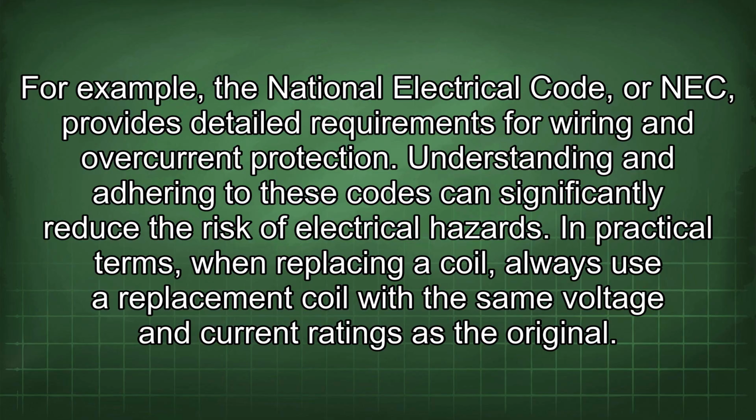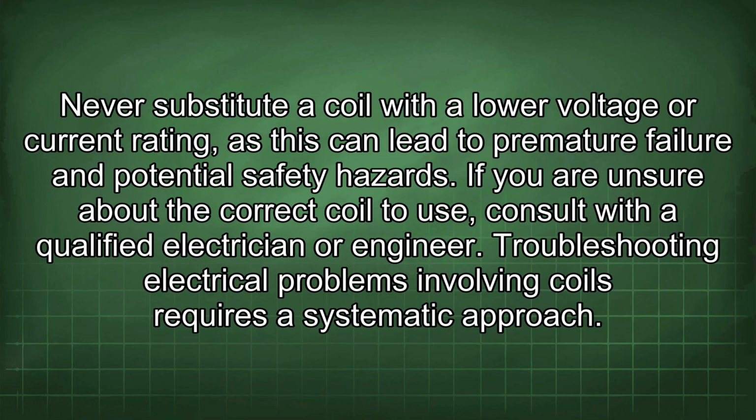In practical terms, when replacing a coil, always use a replacement coil with the same voltage and current ratings as the original. Never substitute a coil with a lower voltage or current rating, as this can lead to premature failure and potential safety hazards. If you are unsure about the correct coil to use, consult with a qualified electrician or engineer. Troubleshooting electrical problems involving coils requires a systematic approach.